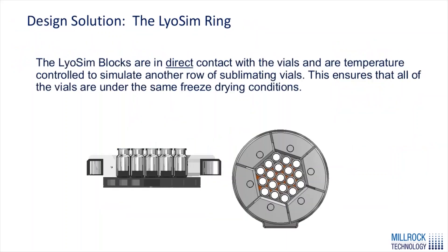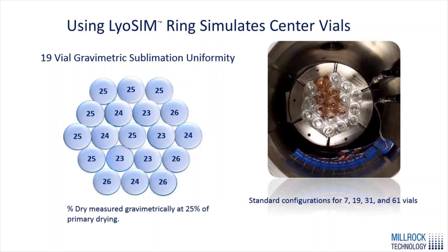The complete design solution is a temperature-controlled LyoSim ring on the outside of the array, with aluminum blocks resting on the ring that bring it into thermal contact with the array of vials. When we set this ring to track the product temperature during the primary drying phase, these blocks on the outside are at the same temperature as the product in the vials, simulating a wider array. Example test results show percent dried measured gravimetrically between 23% and 26%, well within the range of uniformity seen in a full batch.